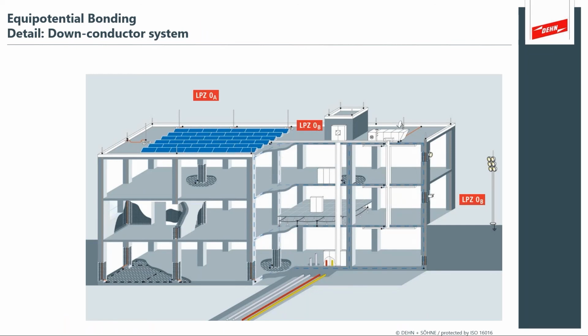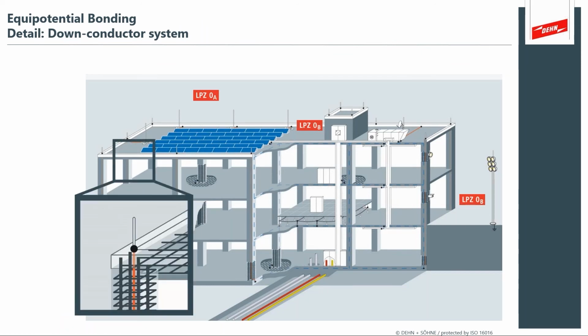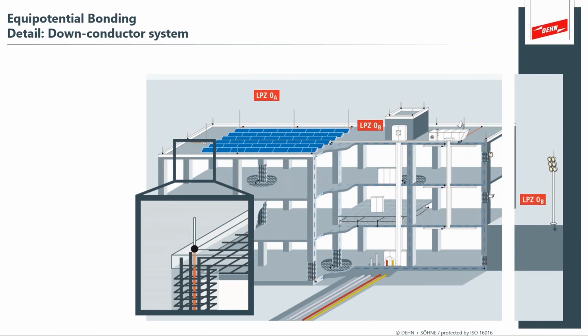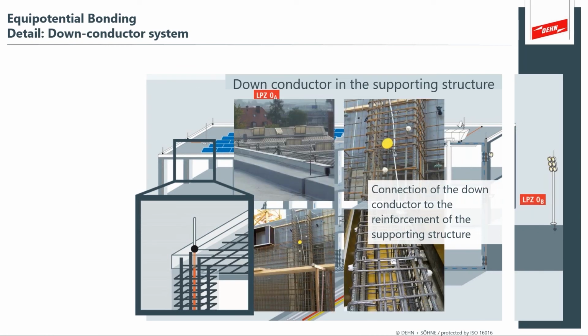So this is a really nice slide because it shows you the external lightning protection system married to the bonding in the earthing system. And what's nice is we can show that the down conductor system is actually embedded in something that looks like that concrete pillar, and we're talking about equipotential bonding, we're talking about earthing, and it's all married together in a well connected and reinforced system.